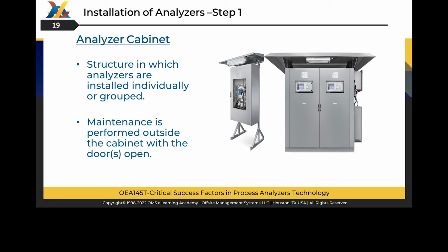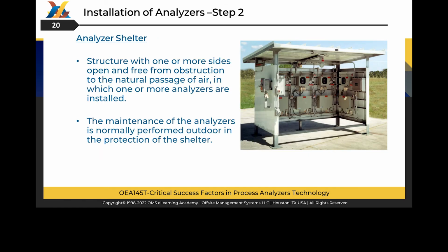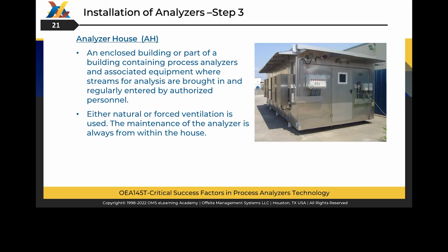The first type of analyzer's housing is analyzer cabinet, which represents a small housing in which analyzers are installed individually or grouped. Maintenance is performed outside the cabinet with the door or doors open. Analyzer shelter is a structure with one or more sides open and free from obstruction to the natural passage of air, in which one or more analyzers are installed. The maintenance of the analyzers is typically performed in the protection of the shelter. The analyzer house, or AH, is an enclosed building or part of a building containing process analyzers and associated equipment.